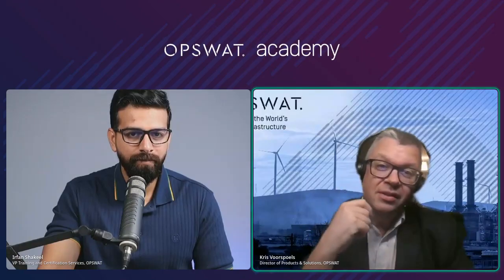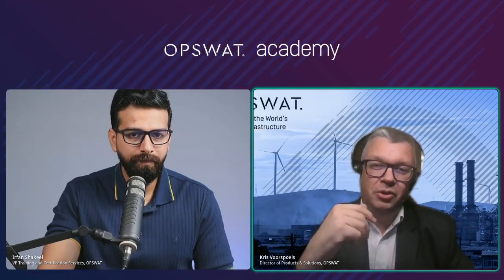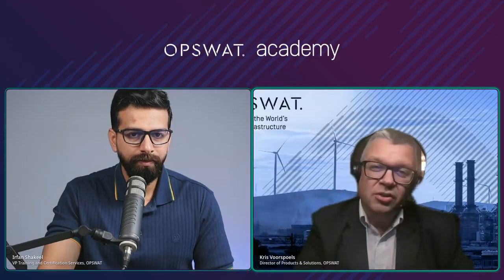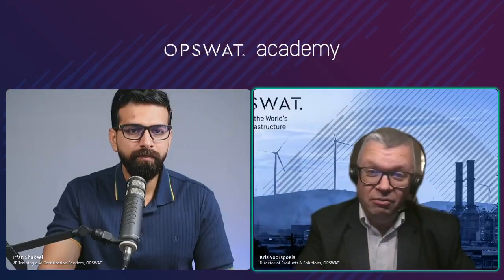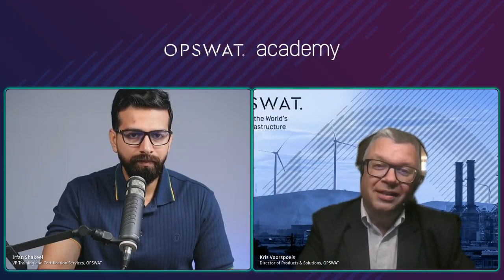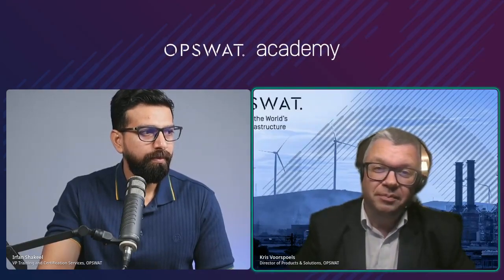So the most advanced systems send the actual data and a piece of historical information for, let's say, maybe the last 8 hours or so, right? So the moment your destination server gets online again, it will immediately start seeing the actual data, so you can see what's going on in your OT plant. And the moment the historical data is received by the destination, it will backfill the data so that there is no data gap, and historical data is restored automatically without going into the operational environment. So it's all automatic. That's great.